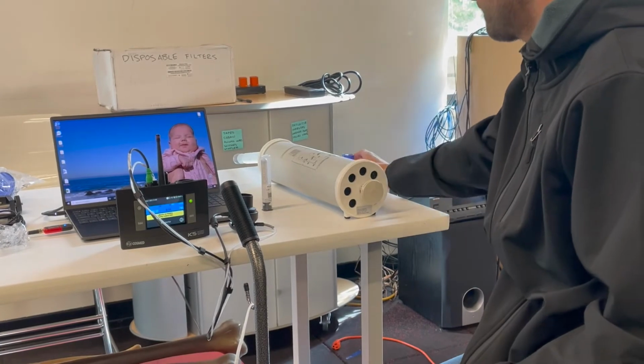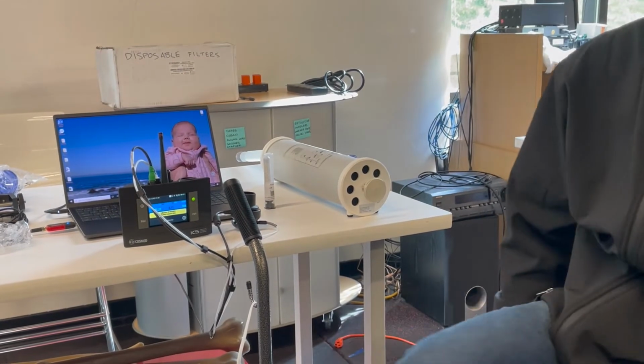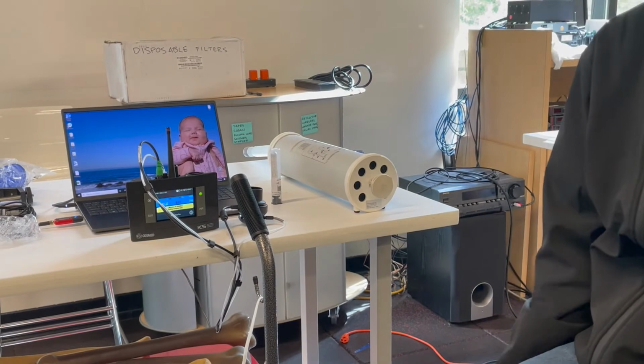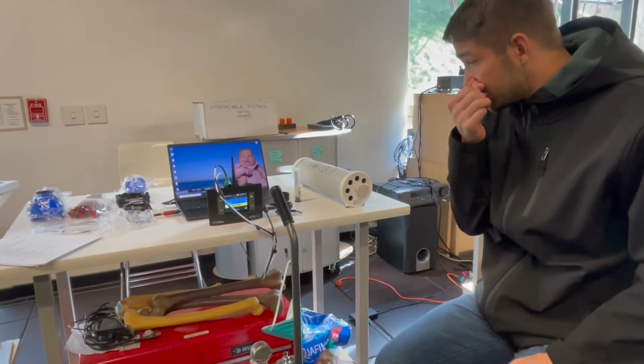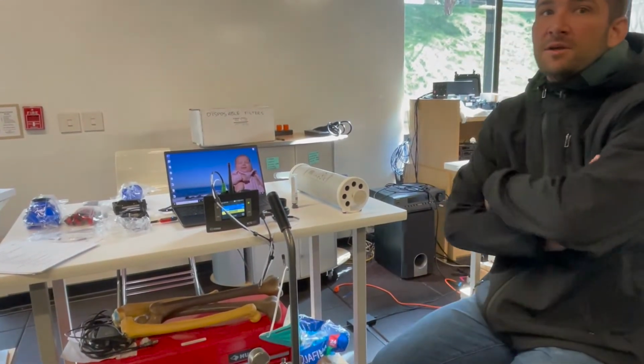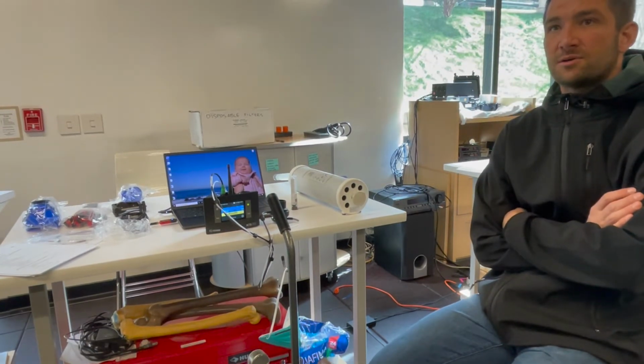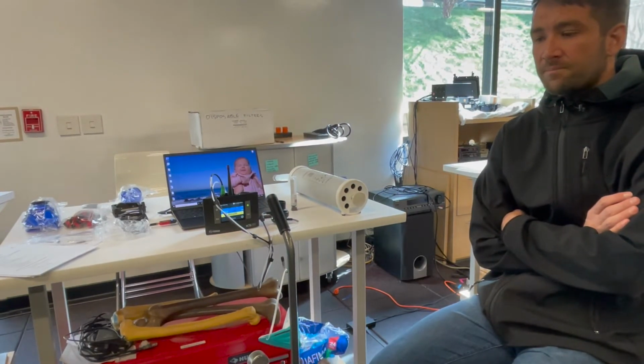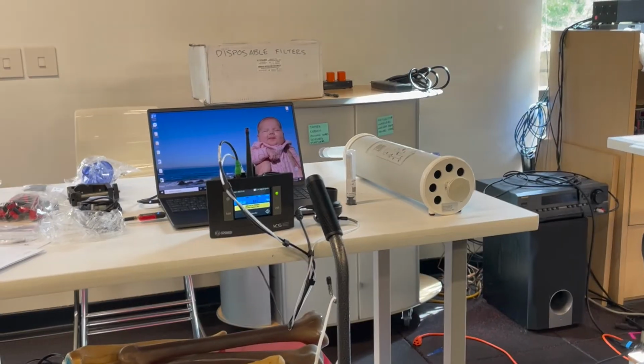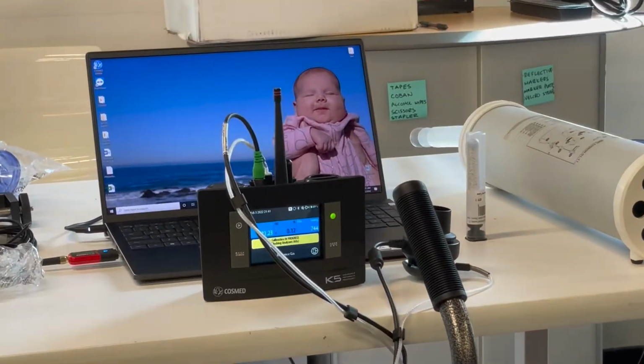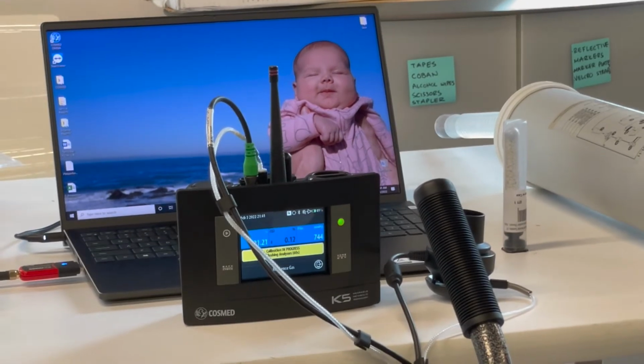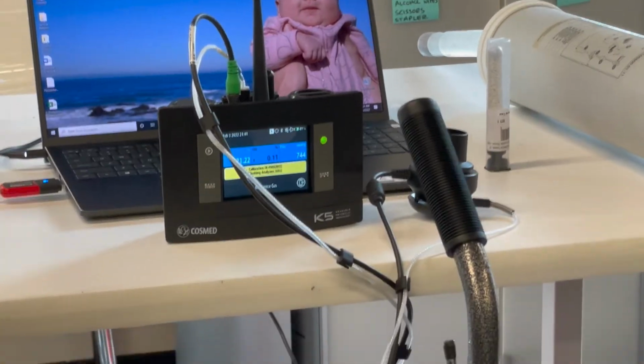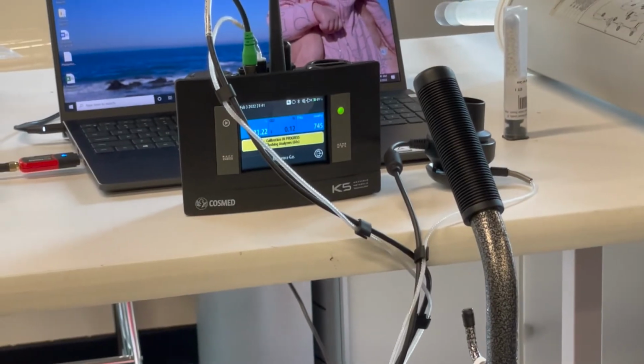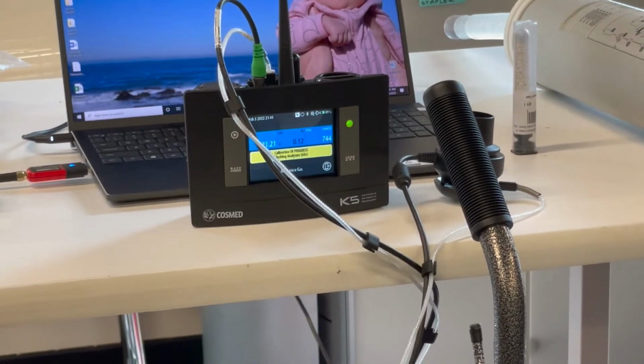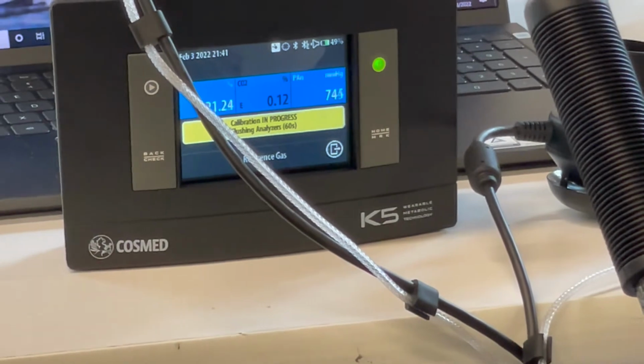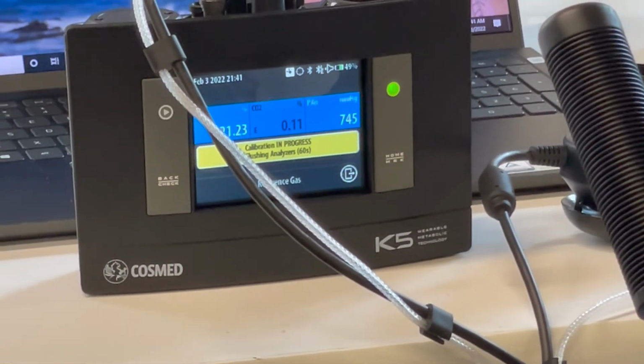So it's using the delay calibration you just did? No, it's not. It's just establishing its own. Yeah. It's just that with the dynamic mixing chamber, you've got to think that it's not measuring the breaths exactly the same so far. You said you get about a year out of the tank? Yeah, with a high level of testing, with lower levels of testing, kind of 18 months, even a little bit longer.